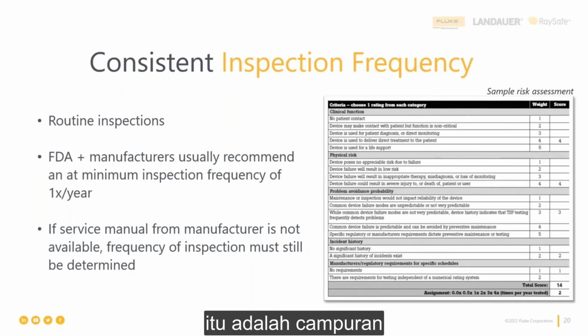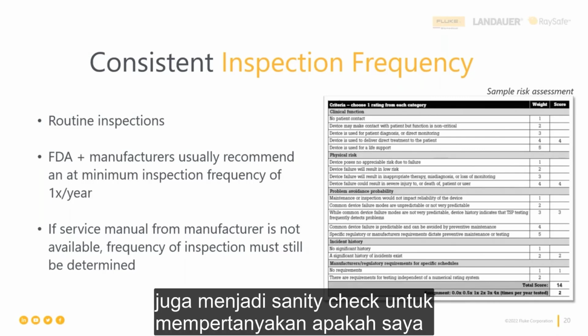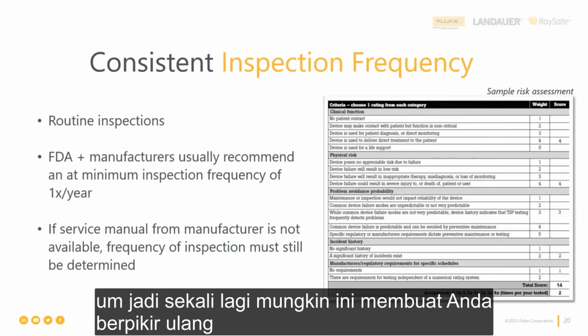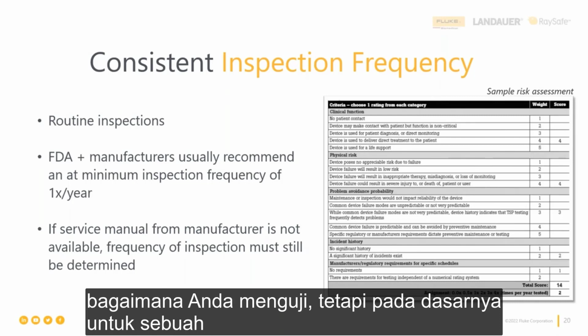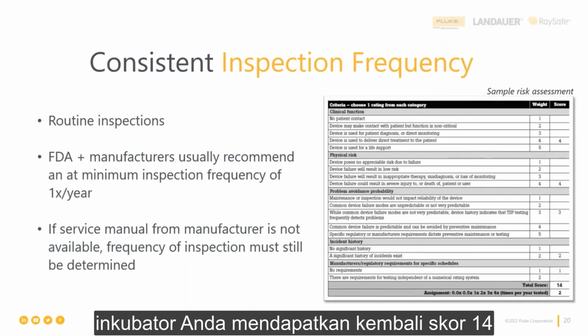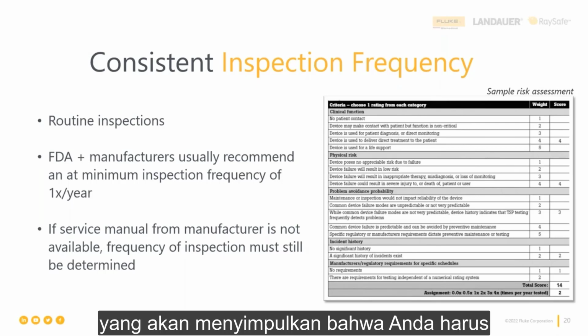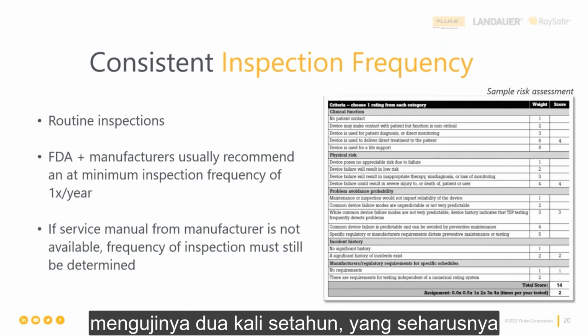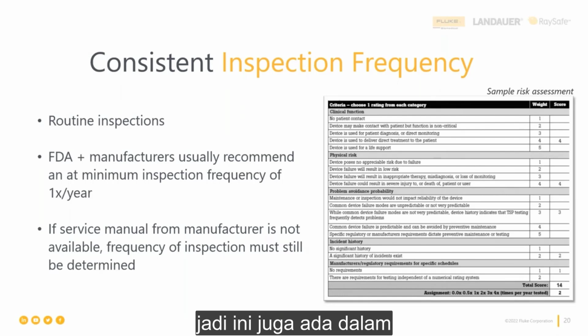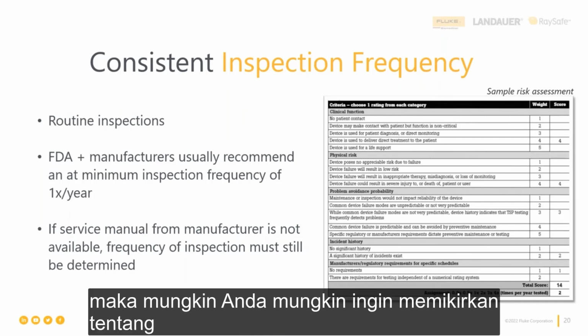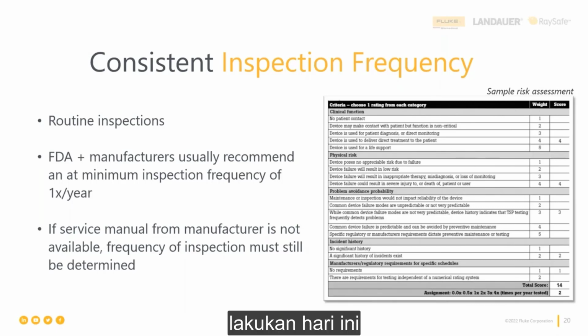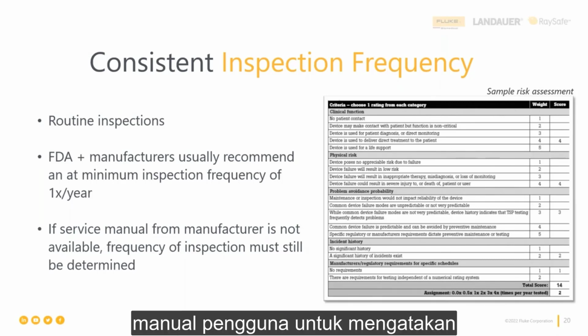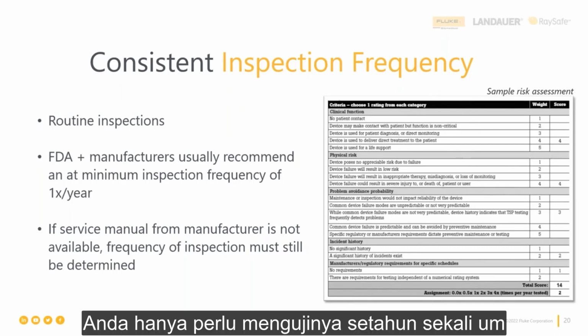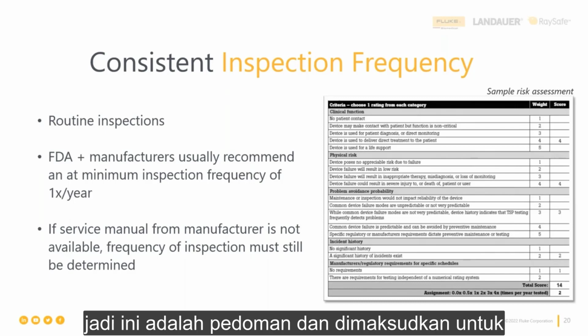This is what you use if you don't have an inspection frequency given to you in the user manual. This could also be a sanity check to say, am I testing enough? Maybe this makes you rethink how you test, but essentially for an incubator, you get back a score of 14, which would infer that you should test them twice a year. That should be your frequency. So if this comes in higher than your user manual, then you might want to think about testing more frequently than you are today. But you can always lean back on the user manual to say that you only have to test it once a year. So it's a guideline, and it's meant to help you.